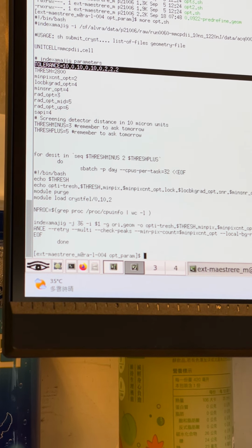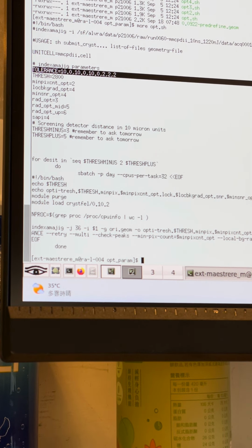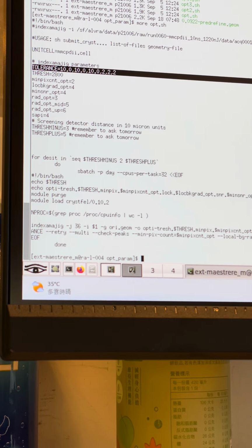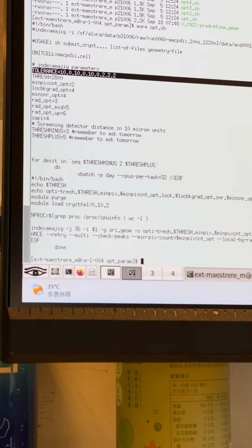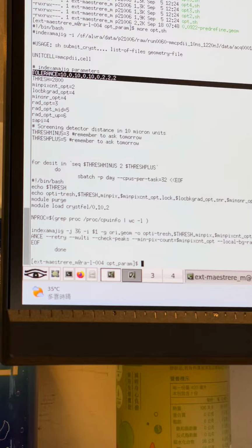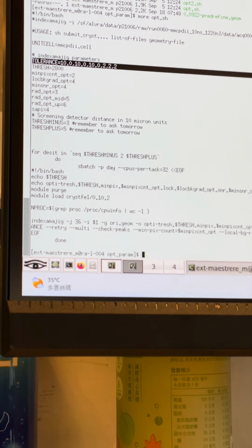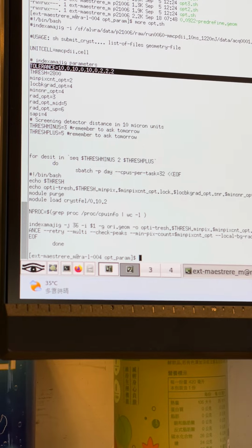So tolerance is the reciprocal space maximum variance from your geometry that the system will accept. So 10 means 10% over whatever the unit cell is that you provided.